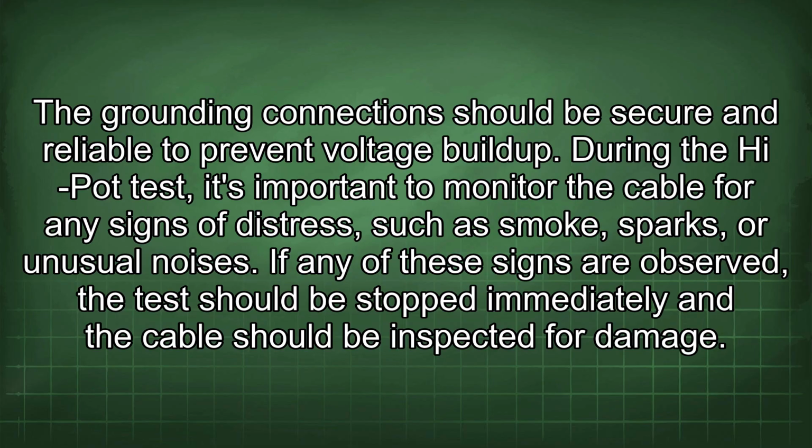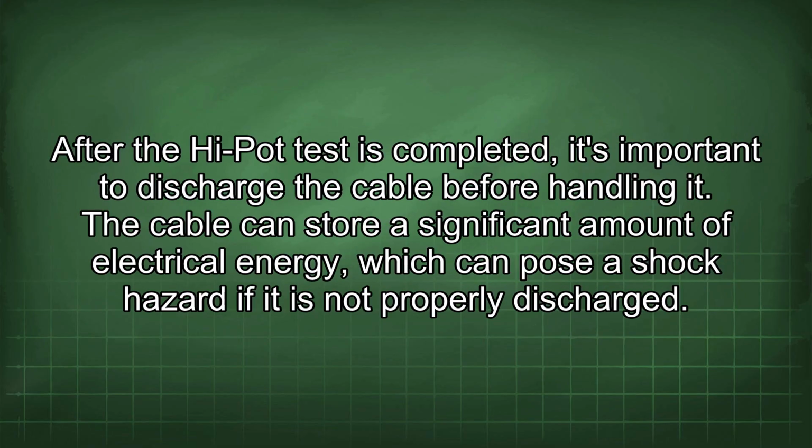During the high-pot test, it's important to monitor the cable for any signs of distress such as smoke, sparks, or unusual noises. If any of these signs are observed, the test should be stopped immediately and the cable should be inspected for damage. After the high-pot test is completed, it's important to discharge the cable before handling it.